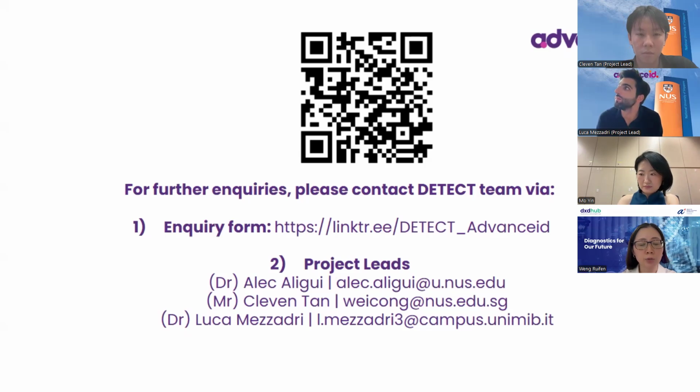So with the reliance program, what this means is if a product registration carries the exact same intended use, and that has been registered in Singapore, there will be an expedited review by the Thai FDA and vice versa. So these are mutual reliance programs. There are also other programs that the Singapore HSA is, I think, working very hard to establish, and we look forward to the official announcement soon to come.